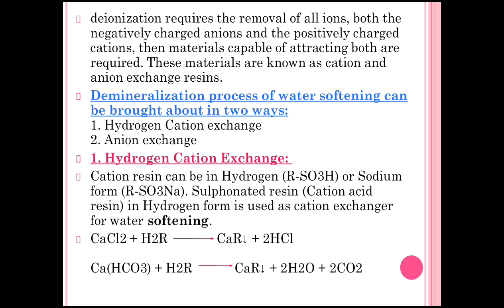The demineralization process of water softening can be brought about in two ways: first is the hydrogen cation exchange, and second is the anion exchange. In hydrogen cation exchange, the cation resins can be in the hydrogen form, i.e., RSO₃H, or the sodium form, RSO₃Na — these are the sulfonated resins. The cationic acid resin in hydrogen form is used as a cation exchanger for water softening. The cation exchange resins are acidic resins because the acid has H⁺ ions; whenever they are in contact with water, H⁺ ions are released and cationic impurities present in water are captured.